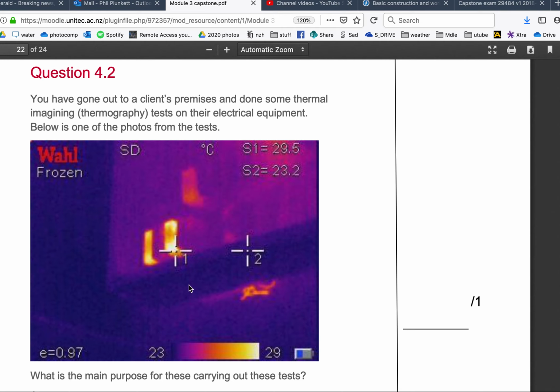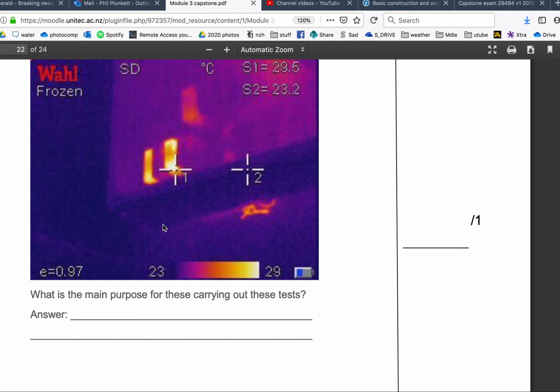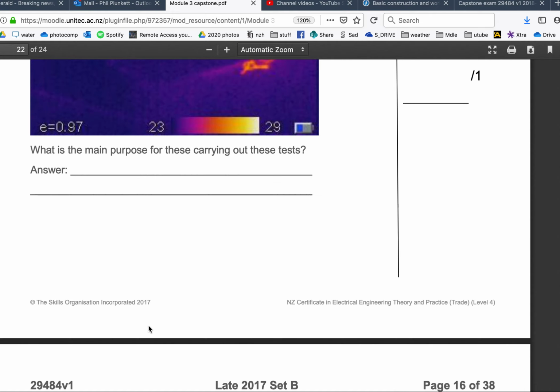This is a thermal imaging camera, so they've put it on the switchboard. They've seen some hot spots here. Maybe 2 of these phases are hot. There might be loose connections or high resistance, or they're putting too much load. So what are you looking for there? You're looking for hot terminations, which indicate high current, which means overloaded cables maybe, or loose connections.